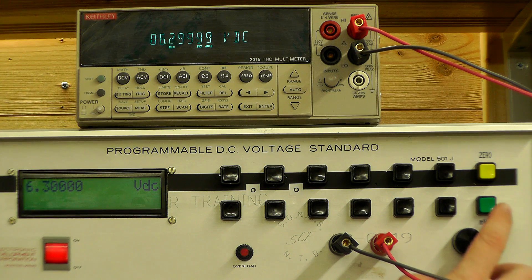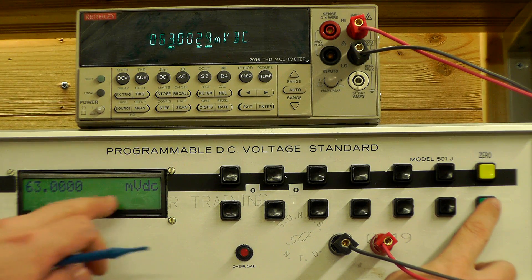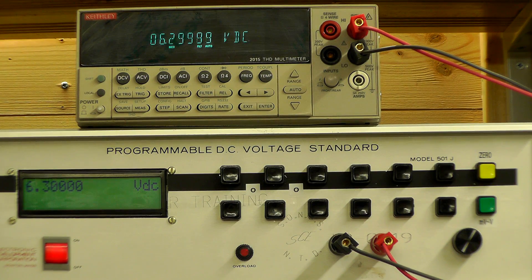And it's a similar thing when you go, if I go back to mode 2, obviously the same thing will happen there. 63 millivolts. And then obviously you're back reading the pot again. So you're basically not really zeroing it at any time.